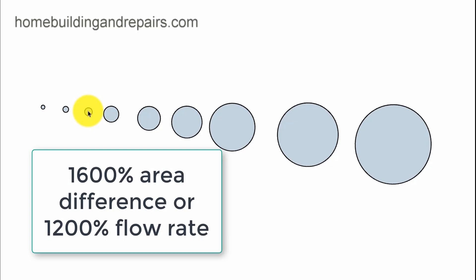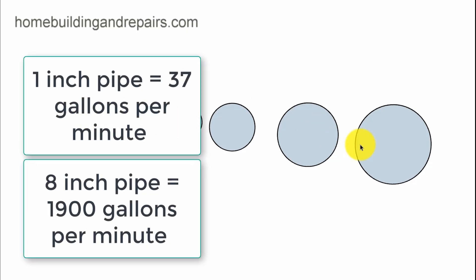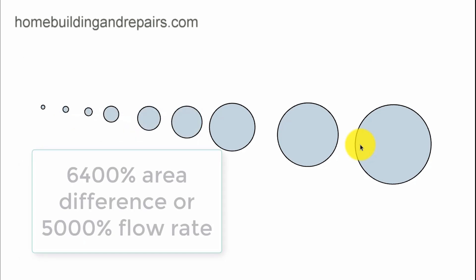A 1,600% increase in volume does not add up to the flow rate. You can't just take the area of a circle and assume that that's going to provide you with the same flow rate, because we have a difference. 1,600% difference in the area between a 4-inch and a 1-inch. And we only have a 1,200% increase in water flow. When we go from a 1-inch to an 8-inch, we have a 5,000% increase in the flow rate and a 6,400% increase in the area of the circle.